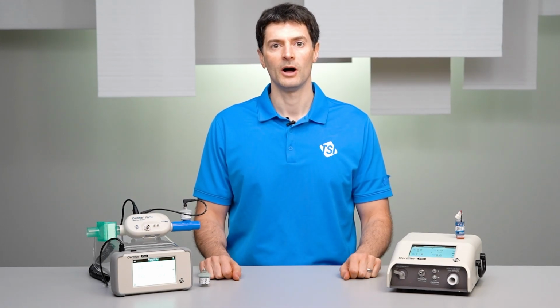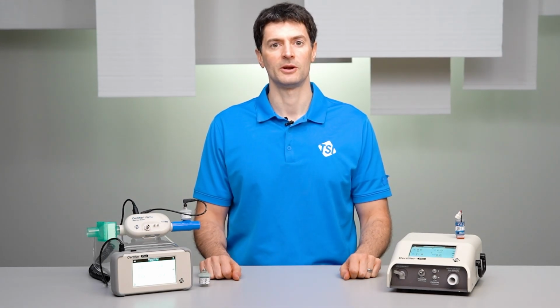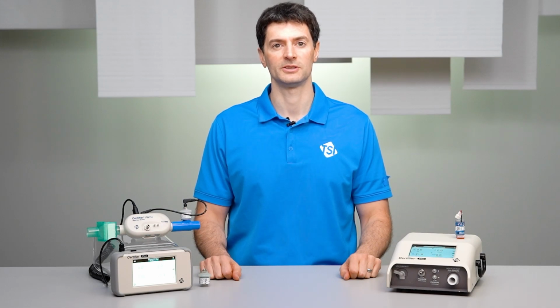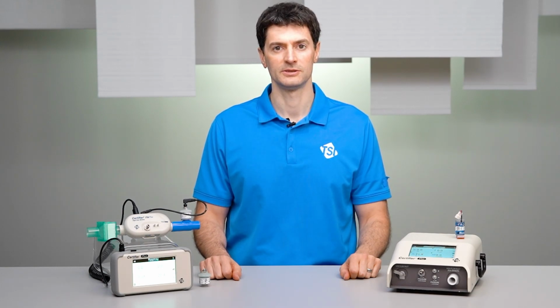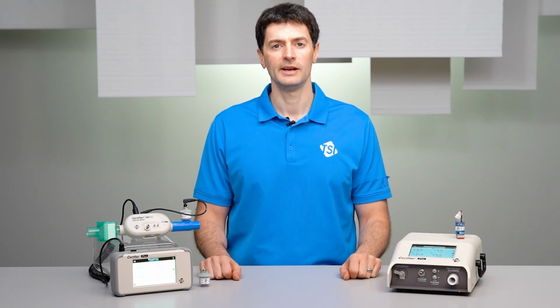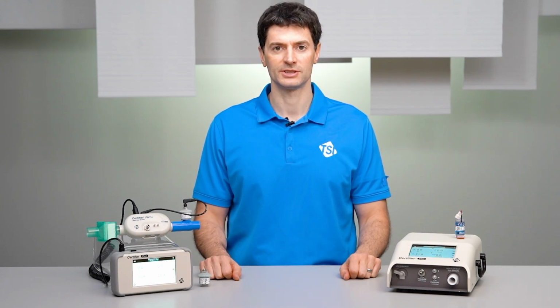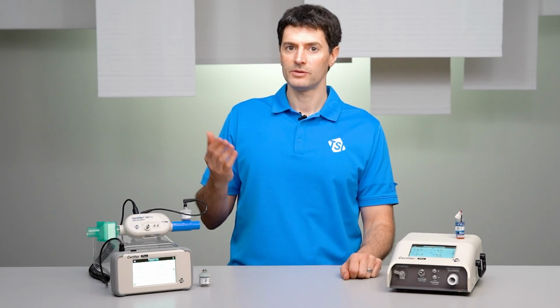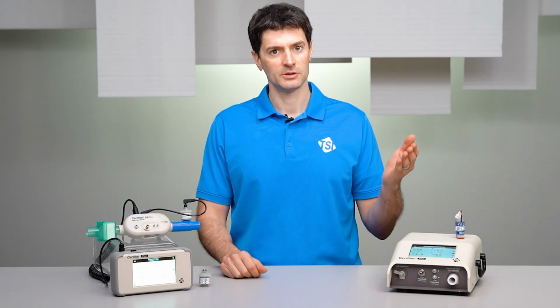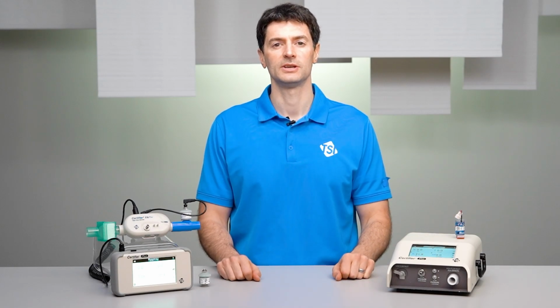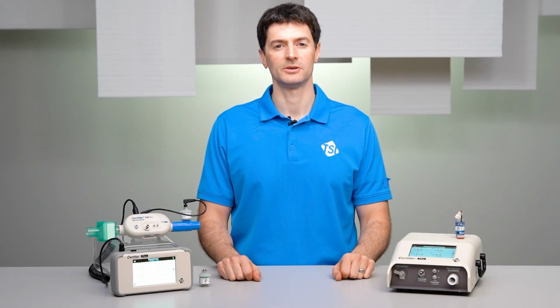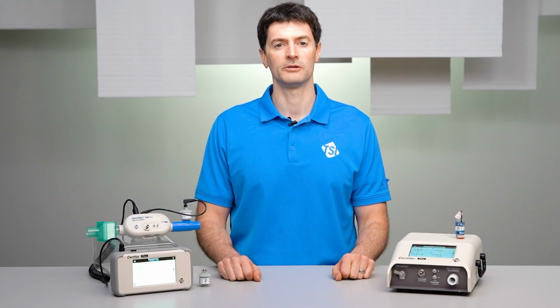In this video, I'll go over the oxygen sensors that are used with our Certifier Flow Analyzer test systems. Oxygen sensor measurements are used to test ventilators, air oxygen blenders, oxygen concentrators, and any other device that outputs oxygenated gas flows. Both the Certifier Plus and the Certifier Pro flow analyzers can incorporate an oxygen sensor to measure the real-time oxygen concentration of gas flows in percentage of oxygen up to 100%.